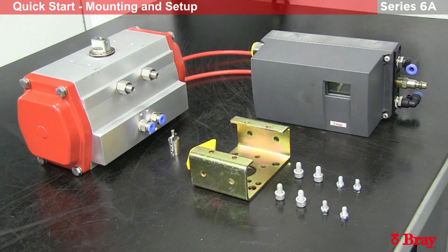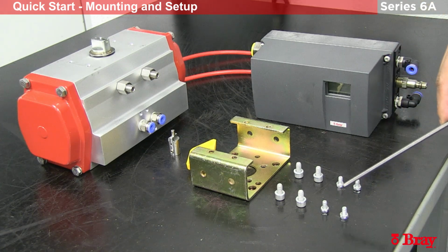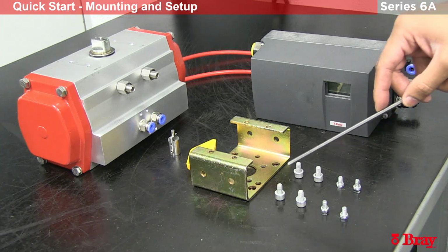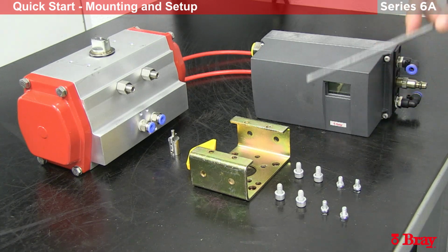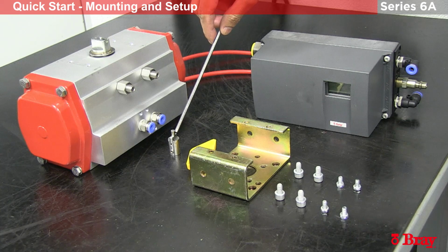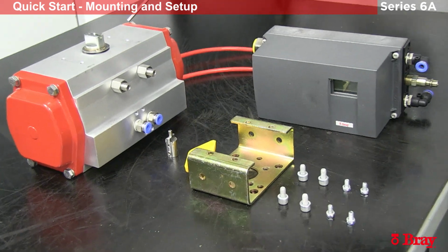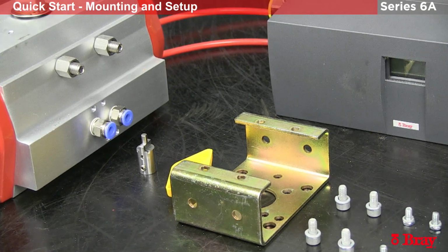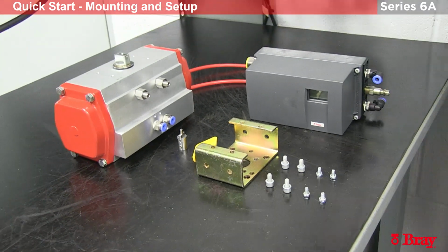This is going to be a how-to video on installing the Bray 6A pneumatic positioner to a rack and pinion actuator. Starting off, we'll go over the hardware that is needed. First off, you'll have your 6A positioner, mounting hardware, nuts to mount the bracket to the actuator, cap screws to mount the 6A to the bracket, coupler for the indicator shaft with indicator arrow, and a rack and pinion actuator. In this case, it'll be a double acting actuator.